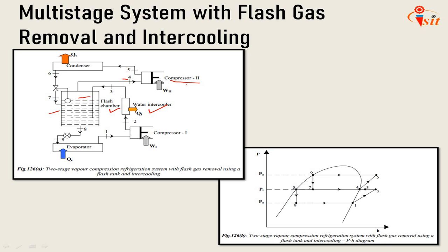One disadvantage of the above system is that since the refrigerant liquid in the flash tank is saturated, there is a possibility of liquid flashing ahead of the expansion valve due to pressure drop or heat transfer in the pipelines connecting the flash tank to the expansion device. Sometimes this problem is tackled by using a system with a liquid subcooler.